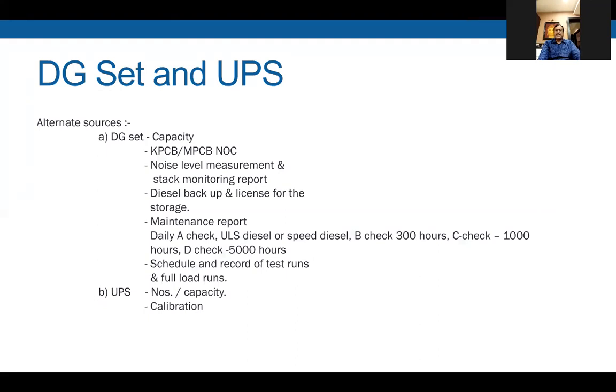Those checkings, the details are generally known to the engineers, that what is the B check, and most of them are being maintained by the companies involved who are providing you with the DG sets. So schedule and the record of test runs must be maintained. Nowadays, electricity goes almost in every city, so there is no need of maintaining separate records because every day there is a shutdown. So automatically DG sets get checked. But one aspect gets always missed is there is another DG set for the fire engine also. That fire engine DG set must be also checked regularly. In terms of UPS, I have made a small checklist which is in the next slide.